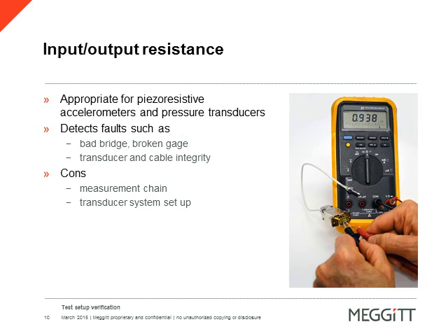Excellent point. This is a very good test method, and I personally recommend it often to test lab professionals. We do need to remember it does not check the integrity of the signal conditioning or data system. It's only validating the transducer itself.